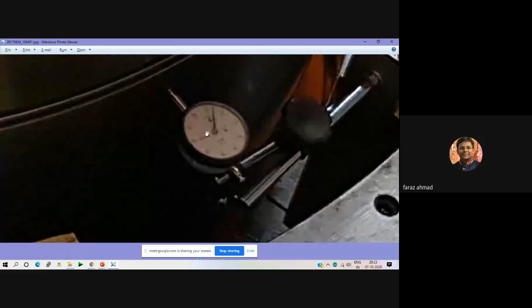Now, as I told, there are no ball bearings and stuff, so we use guide bearings. This is the guide bearing housing, yes, the yellow painted structure. And what you see here is the process of aligning the machine. So vertical alignment is being done. We have approximately 6 to 8 micrometers installed, one over here and the other opposite to this, one over here, the other opposite to this, and then opposite over here. So all these help in making the alignment perfectly vertical. There should not be a single error, because if the orientation of the shaft is not perfectly vertical, it will create stresses on different guide bearings, raise their temperature, it will heat up the oil, overheating will be done, and the machine will collapse.